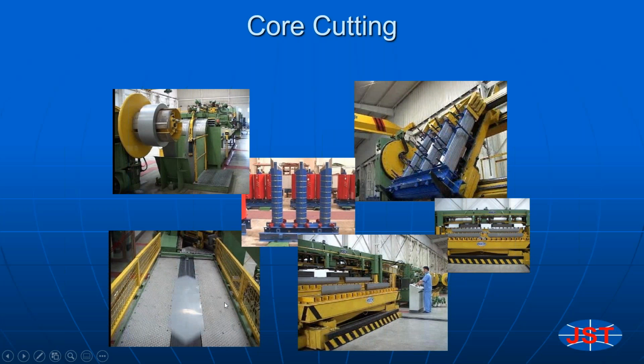Okay, core cutting. Basically, I think they call the geometry we're after when we build the core cruciform. I'm not really sure what that ever meant, but what we want to do, it's a round core. So we basically buy the steel directly from the mill, and we're going to slit it into different widths. And so the idea is that if you take a series of different widths and you start on the bottom with a narrow one and slowly build up to the middle with wider widths, and then start to stack with narrower widths, you eventually get a round form. So that's basically the idea of the different widths.